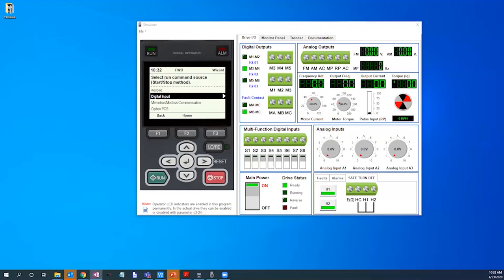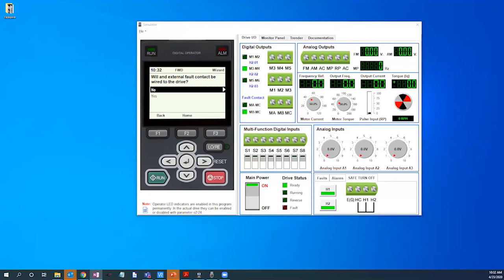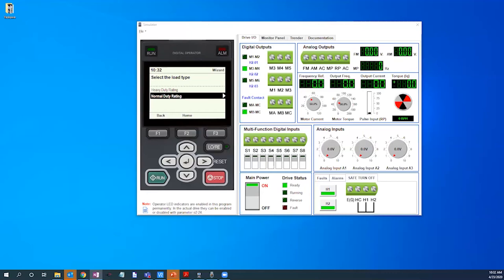Next, select digital input for the run command source with 2 wire factory default control. Press enter again to advance. Select no for an external fault contact. We will use normal duty for this example with no braking option to control an induction motor with volts per hertz control by keeping the selected control method.